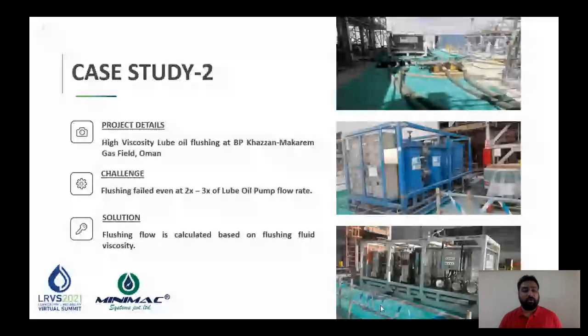This is a case where it becomes very important, while calculating the turbulence, to take care of the viscosity of the flushing fluid. If you don't do that, and just go by a thumb rule of 2x to 3x the flow rate, you will probably miss out on the actual flushing in your system.